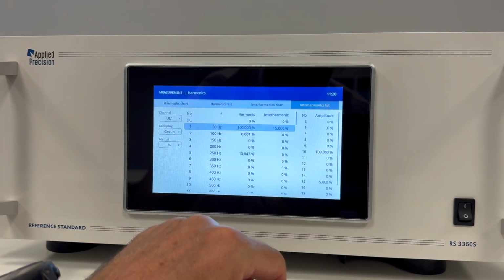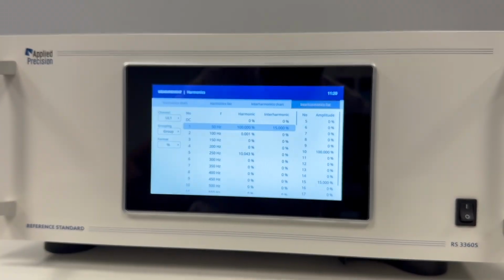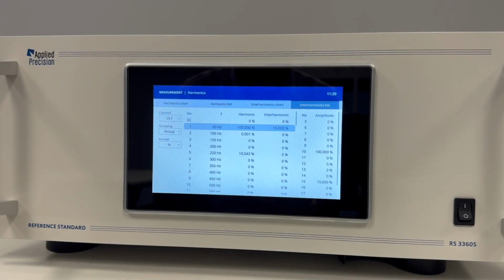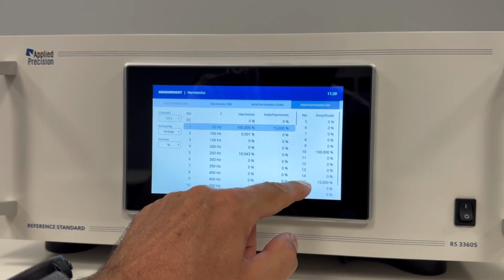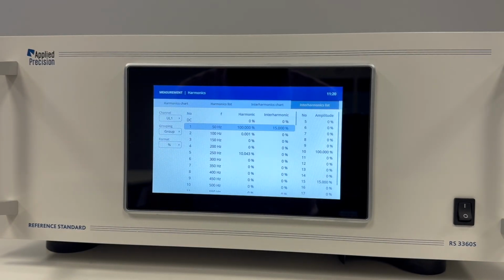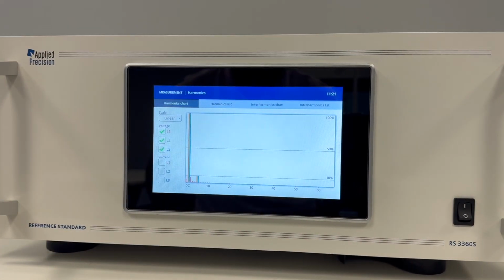15%. And by the theory, it's more complicated, how interharmonics are represented by multiples of frequencies spread into a 5 Hz interval. So it is related to 15 multiplied by 5, which is 75 Hz, and it is 15% measured here. So this is how we can also see the interharmonics.